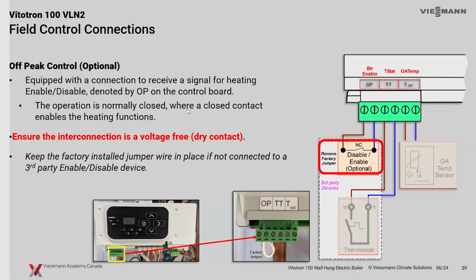So this little jumper called OP is for off-peak operation. If you're on that type of program and you want to make sure the boiler will not operate during those peak periods, you could have a timer or whatever connected to the OP terminal. So it opens during the time of day that you don't want to use the boiler because electricity costs a little bit more, and it closes during the times that you'd be able to use the cheaper power based on that program.